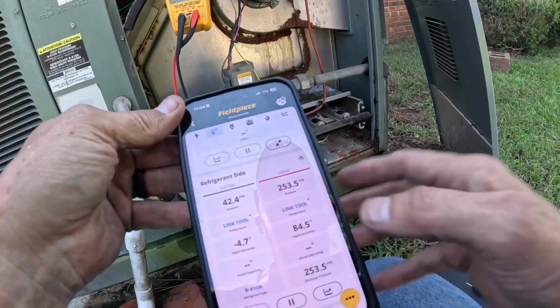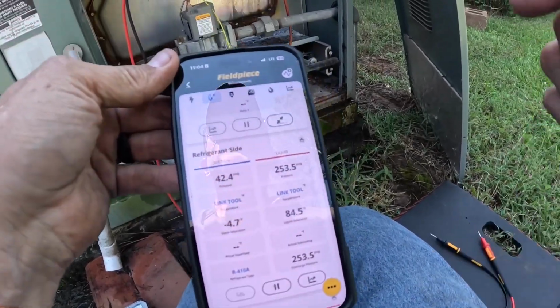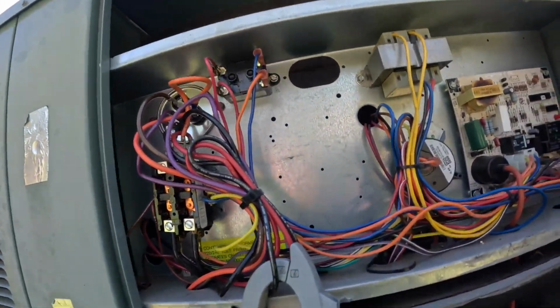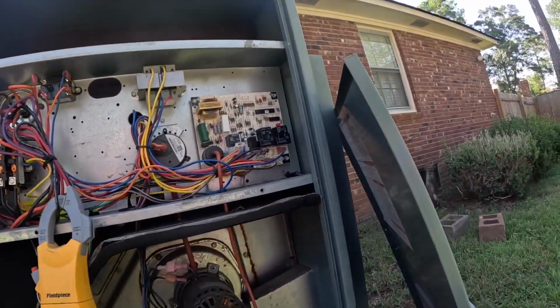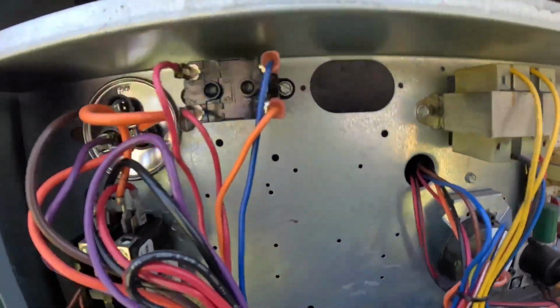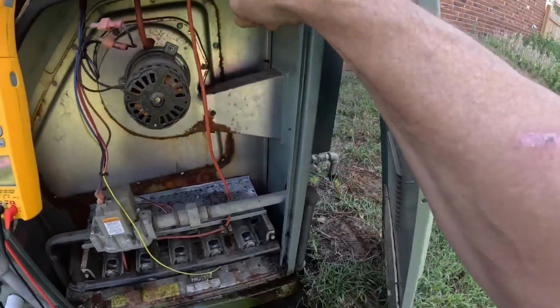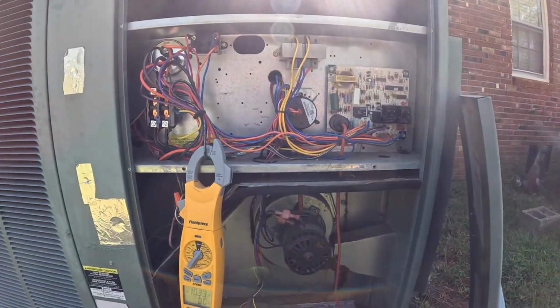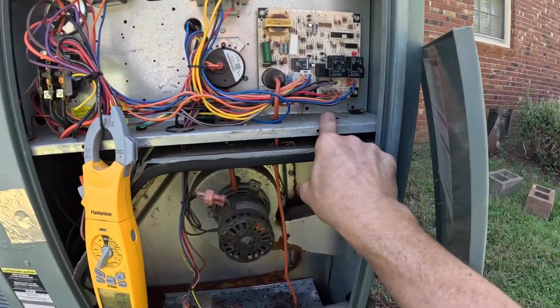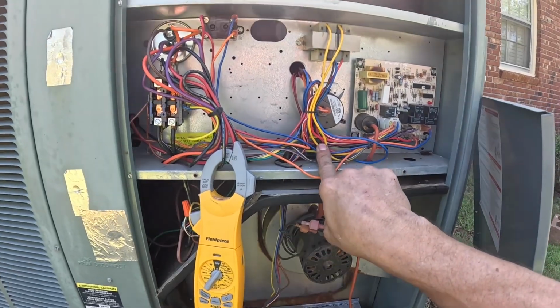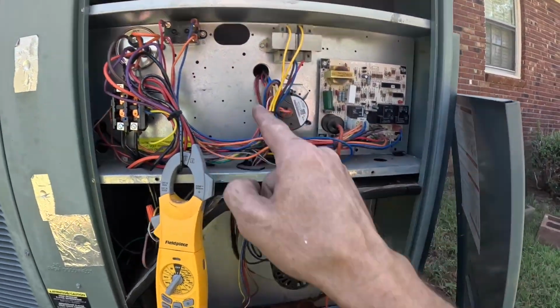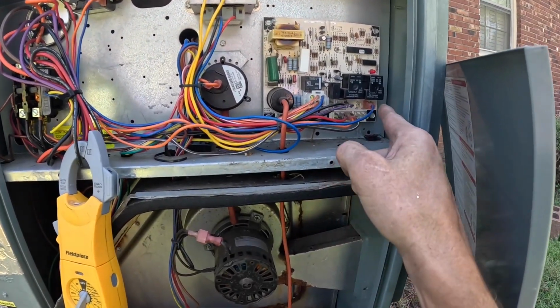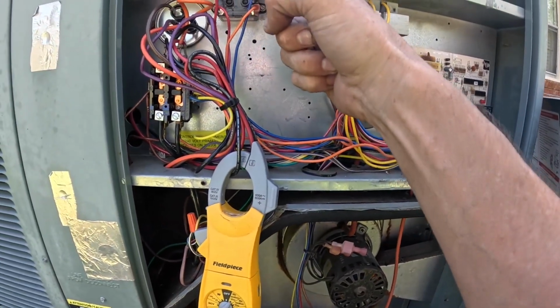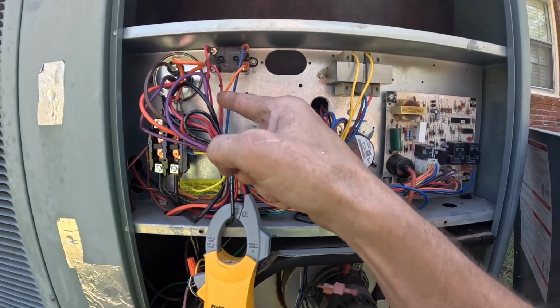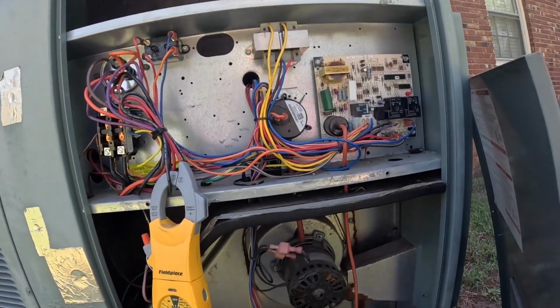That is quite low, and it makes me wonder if the blower is running. Now this is an ECM motor, but we use the same old board. So what they do is they use low voltage for most speeds, but for heat it sends 240 volts to this coil and passes low voltage to the motor. Let's go check that motor real quick.